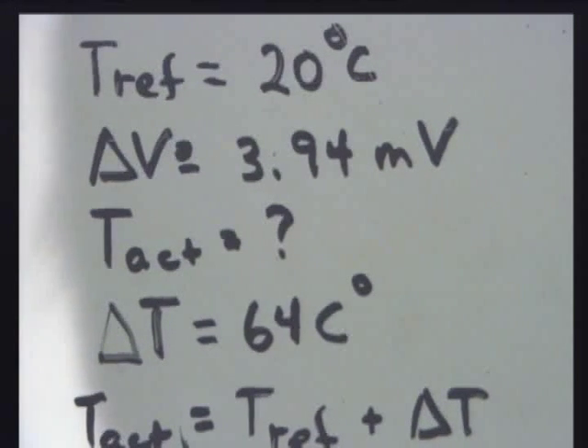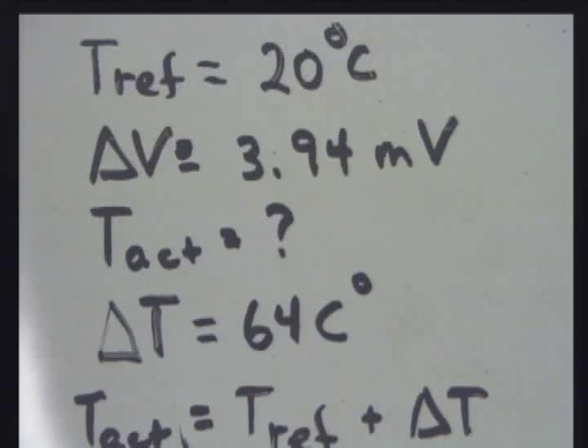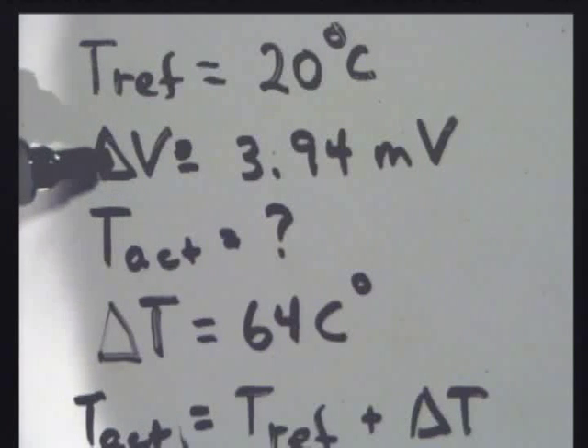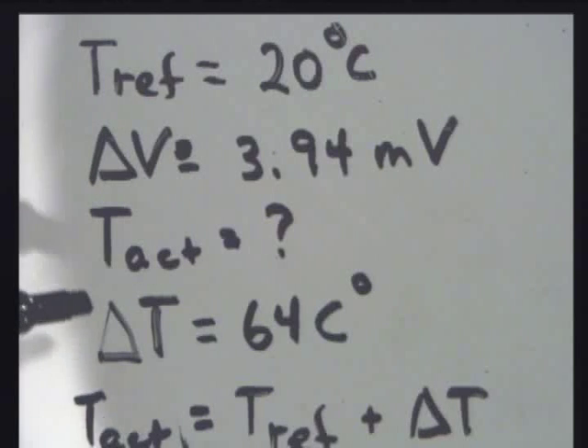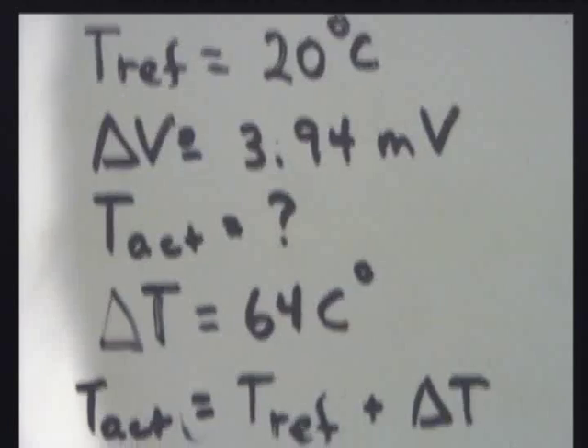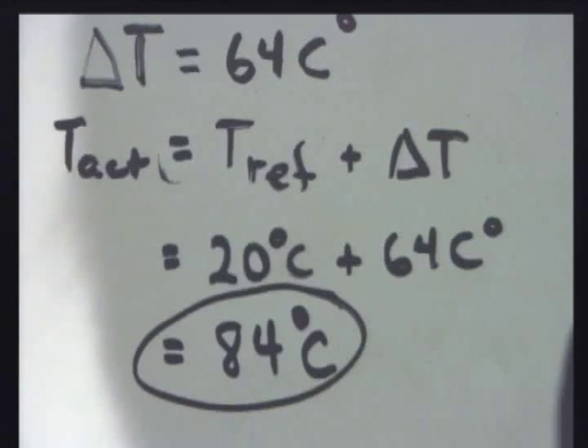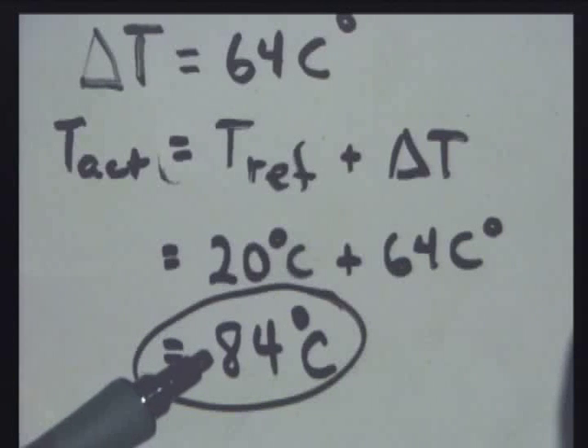Let me go through that one more time. Reference temperature of 20 degrees Celsius. Voltage difference measured of 3.94 millivolts. I want to know the actual temperature. I look up this value in the thermocouple chart. I find 3.94 millivolts corresponds to a temperature difference of 64 Celsius degrees. The actual temperature is the reference temperature plus the temperature difference, which is 20 degrees Celsius plus 64 Celsius degrees, gives me an actual temperature of 84 degrees Celsius.